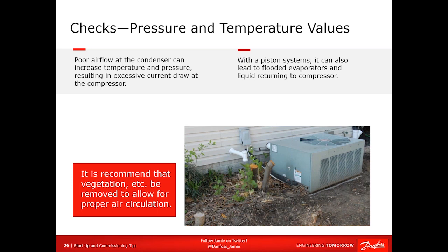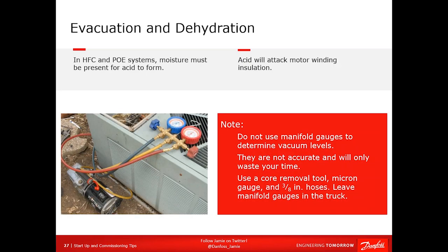If you eliminate airflow at your outdoor condensing unit, expect real problems. And if you have a piston metering device, a simple restriction metering device, it's quite likely that you're going to flood that compressor, and we'll show why in a bit. So a lot of dead compressors can be traced back to poor airflow at the condenser. Now, this is a pretty easy thing to pick up with your eyes, all right? If it's making noises, if it's wobbling, if it's visibly going to have no airflow because it's being blocked, address that right away. It might not even have been part of the service call, but it will make the system operate a lot better and possibly protect the compressor.